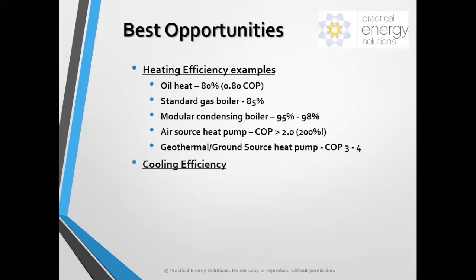Cooling efficiency is even better than the heating efficiency. With a typical rooftop unit direct expansion air conditioning system, you can get a coefficient of performance as high as 2.8, and this is pretty standard equipment. A packaged unit, something like that, that sits on your roof and can provide heat and air conditioning, or air conditioning only. But as you get to the air source heat pump, your coefficient of performance can get up to 5 or even higher. And that air source heat pump is pulling heat from the air inside the building and taking it outside the building. And the way the heat pump is set up, that can be very efficient.